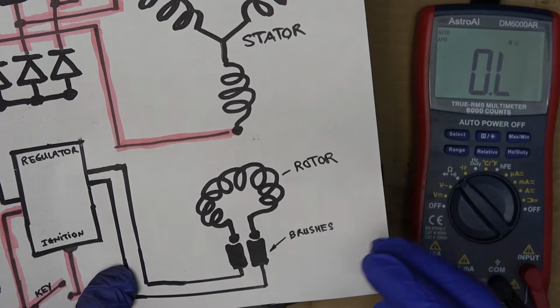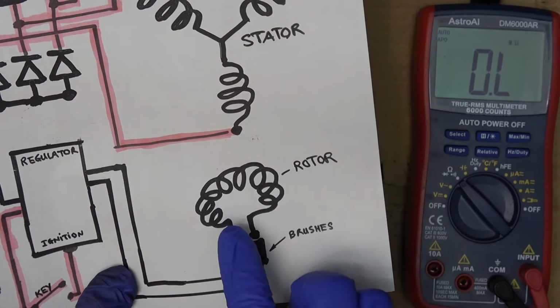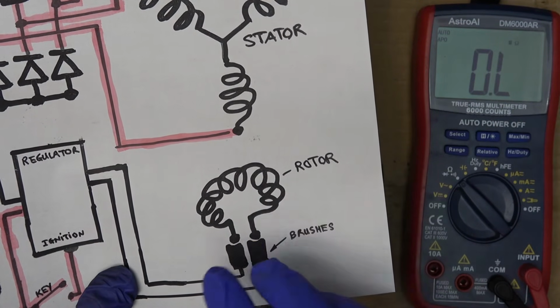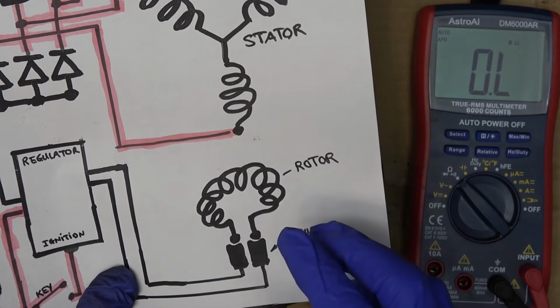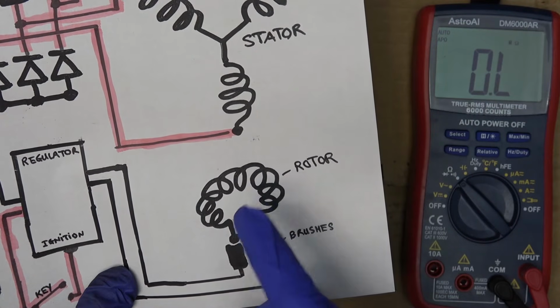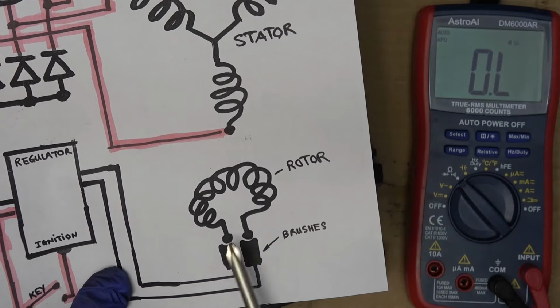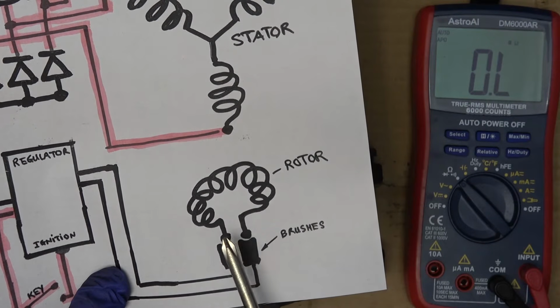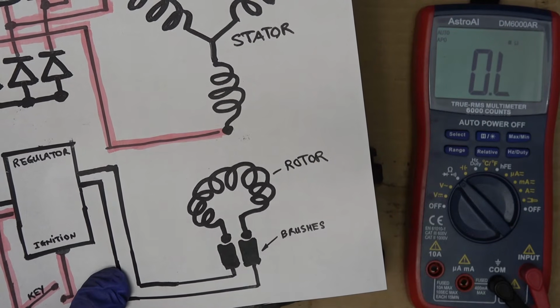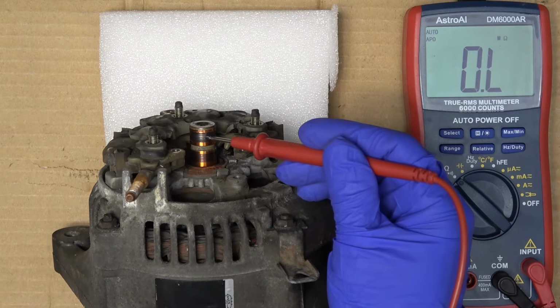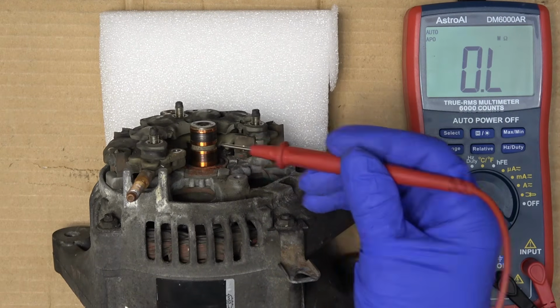I'm going to measure the resistance on the winding of the rotor to make sure it's in the normal range and there's no cut on the wires. These 2 points here on the rotor are the 2 slip rings on the shaft - this ring on top and this ring on the bottom.